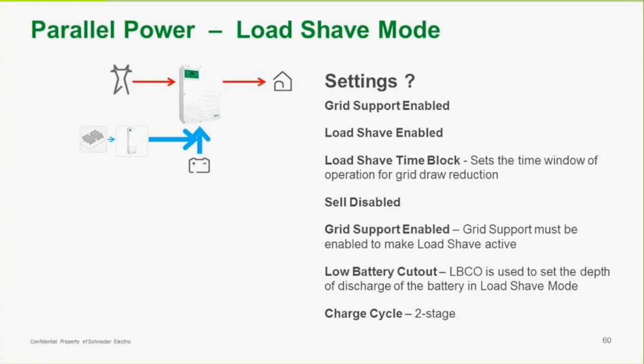In parallel power, we're providing load shave enabled. We have set load shave time block. We have sell disabled. We're not selling to the grid yet. We have grid support enabled. We have a low battery cutout. We have the battery set on 2-stage cycling. So now we're able to use power from the grid as well as power from the batteries. And that'll happen depending on how we have our load shave time block set up, and so on.